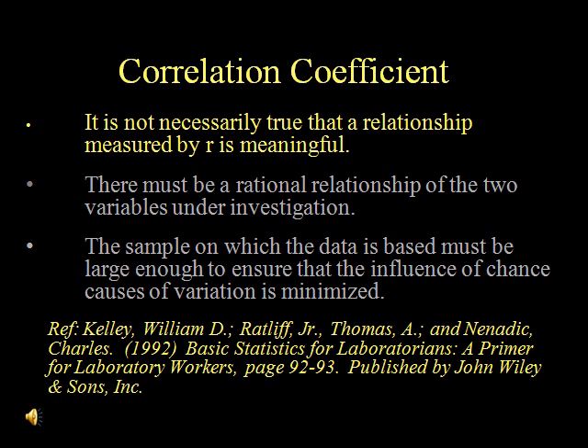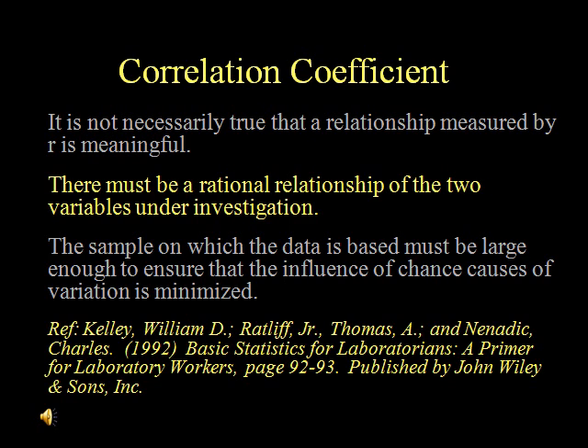It is important to note that the relationship measured by the correlation coefficient, or R, is not always meaningful. In other words, a 0.995 or better does not mean that the calibration curve is acceptable. In order for the correlation coefficient to mean anything, the relationship between the two variables should make sense and should be related. An example of non-rational correlation is the one between the rise in teachers' salaries and the consumption of hard liquor in the U.S., which resulted in a correlation coefficient of 0.98.